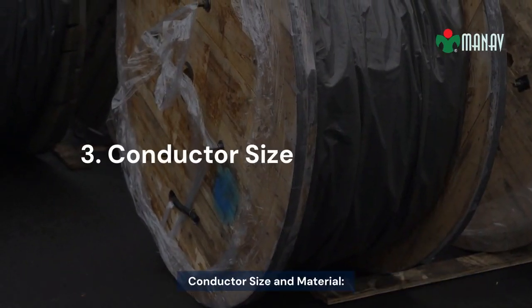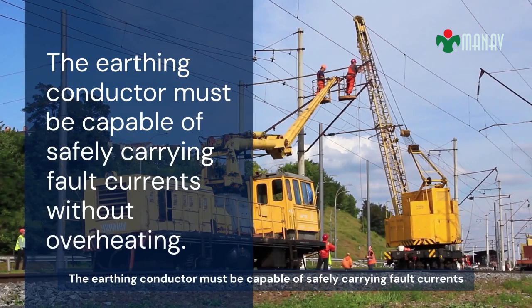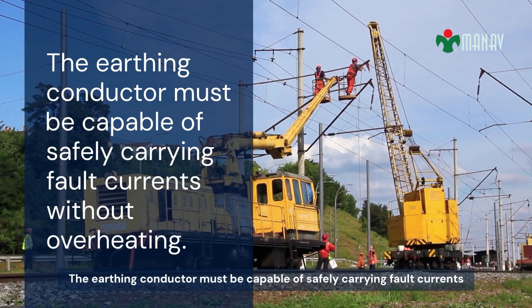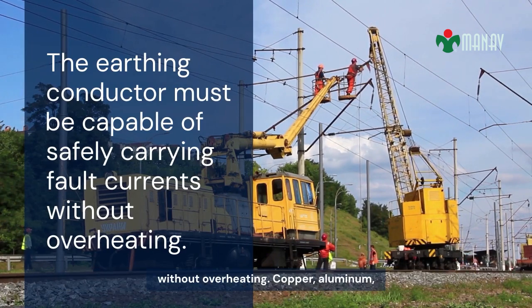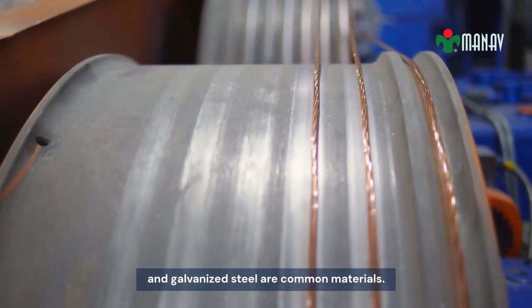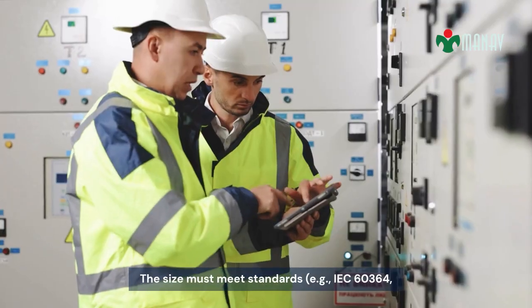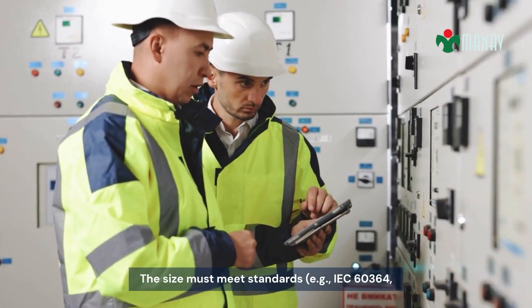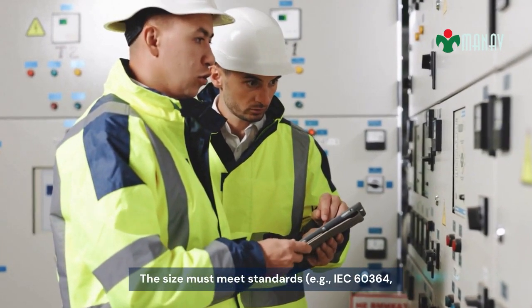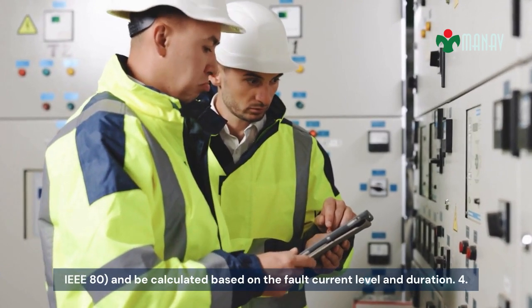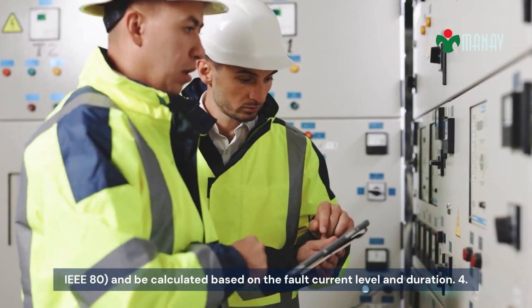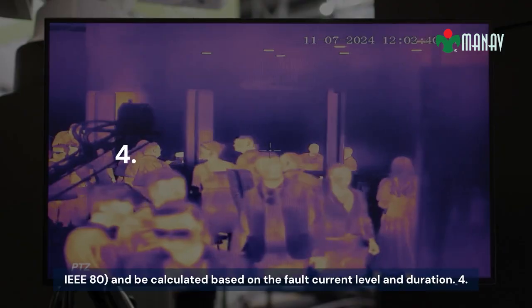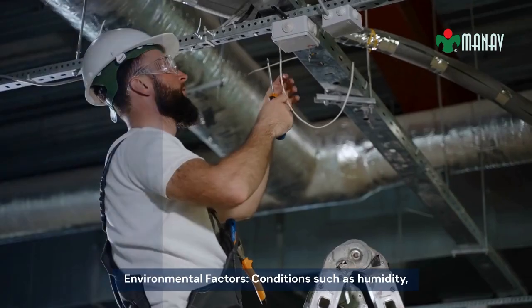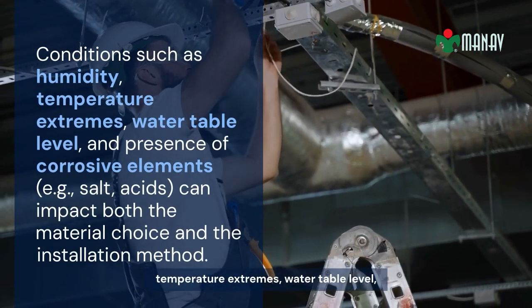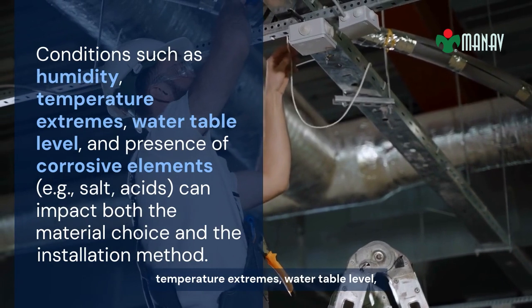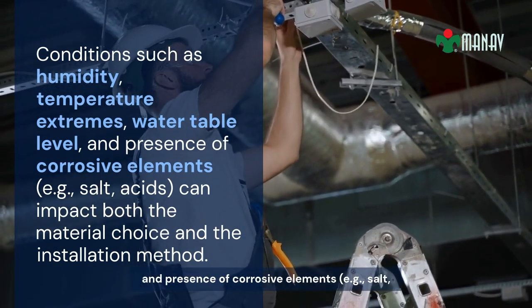3. Conductor size and material. The earthing conductor must be capable of safely carrying fault currents without overheating. Copper, aluminum, and galvanized steel are common materials. The size must meet standards, e.g., IEC 60364, IEEE 80, and be calculated based on the fault current level and duration.